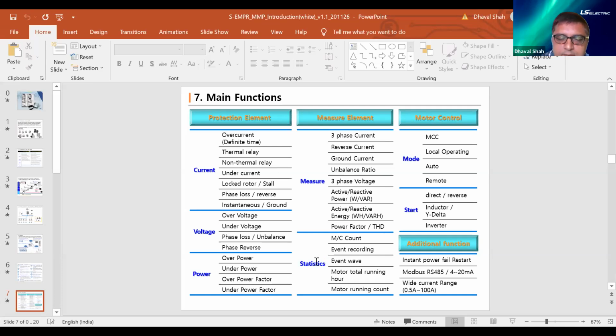And again, statistics, as I said, are advanced analytical settings. So you have event recording, and you get predictive maintenance. Since it is overcurrent, you can set it at some predefined level, so before damage can occur, you can set it for, let's assume, 75% or 80% of the load factor. It can be controlled from a remote station. It can be controlled from the motor control center. It can be auto reset or remote reset. And for starting functions, you can use direct, reverse starter, star delta starter, and inverter starter.